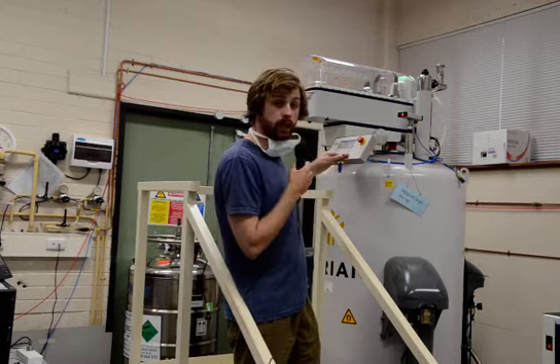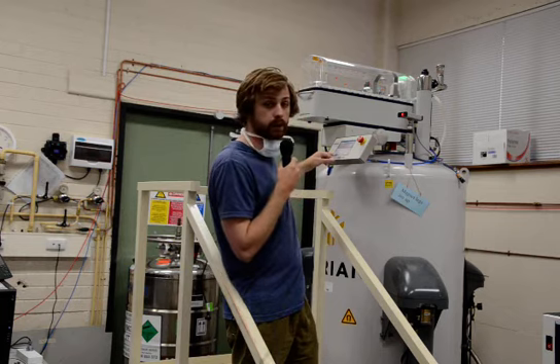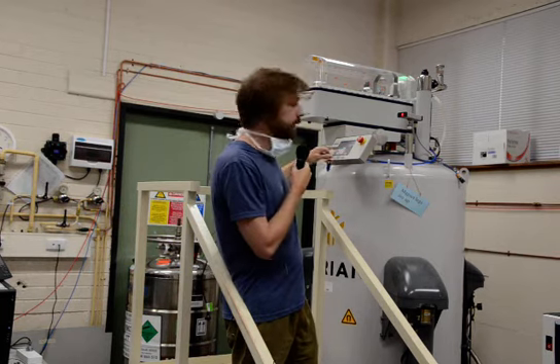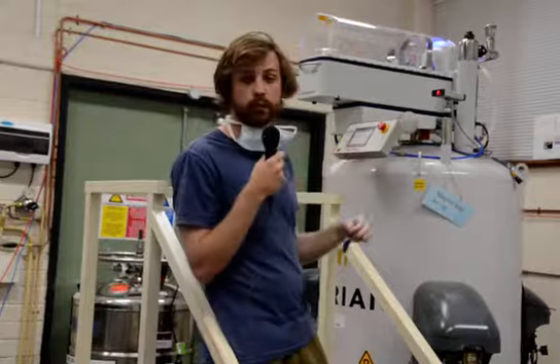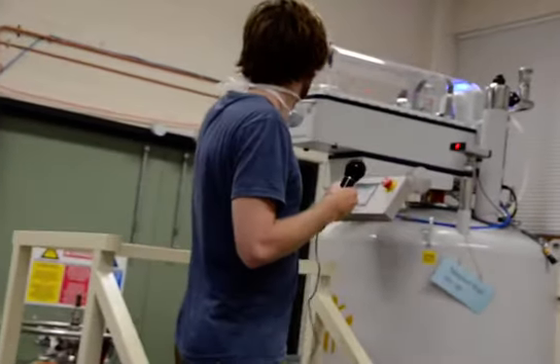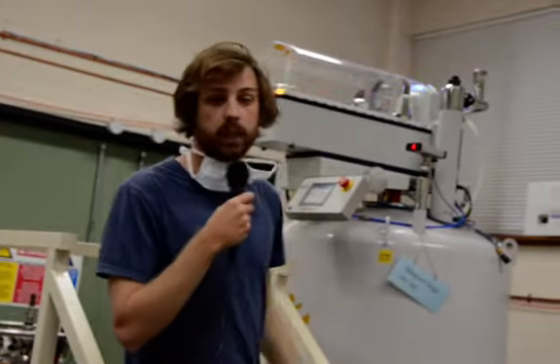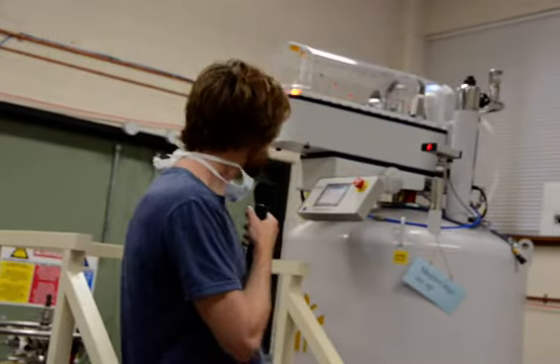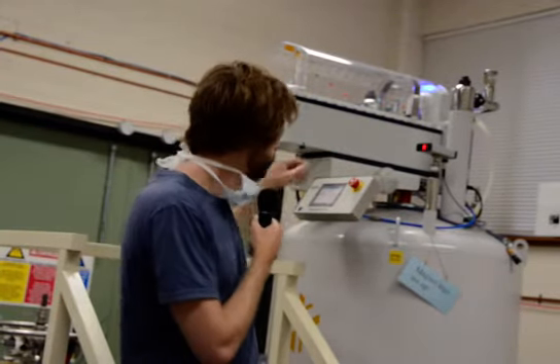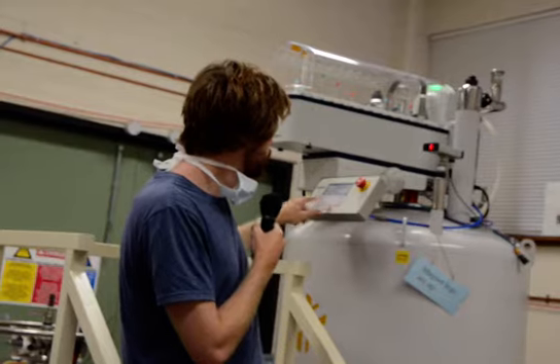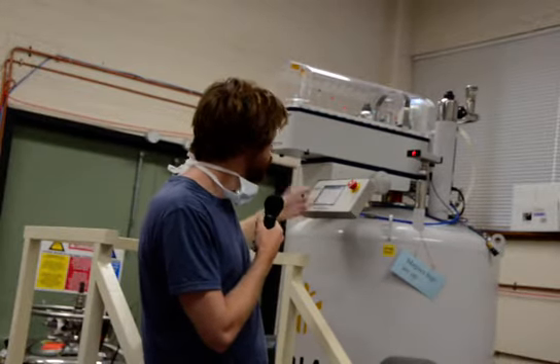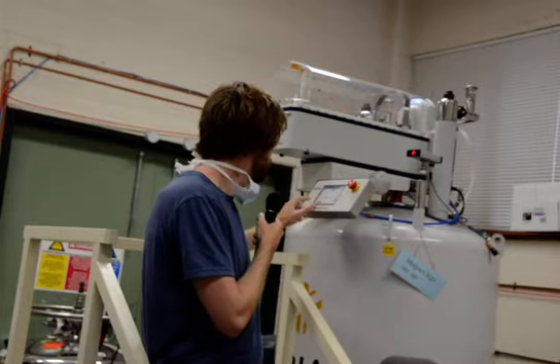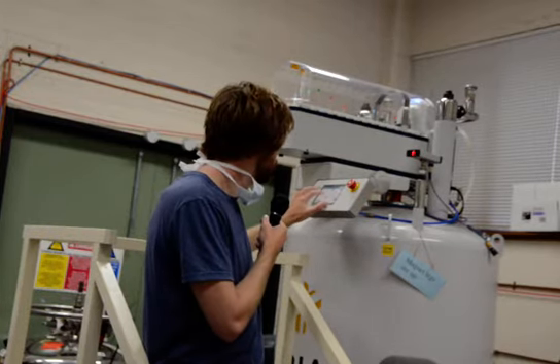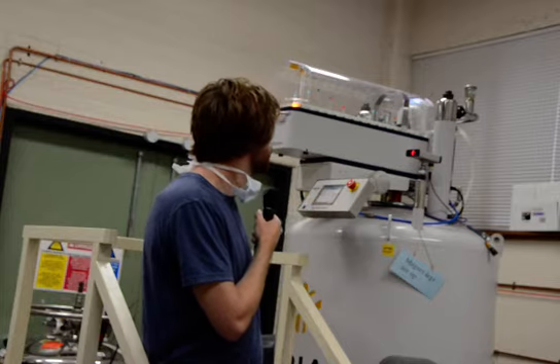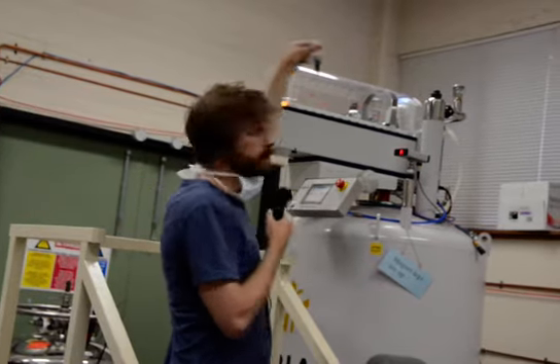So what we're going to do is hit add on the little panel here, which is a little touch screen. We click go to free, so that'll set it up to go to a free sample holder, which it's already at. Place the sample in the spectrometer carefully, and then it's going to go to the next free sample holder. What we can then do is remove the sample too, just by hitting the remove button and then remembering the position of the particular sample. So in this case here, it was 34. And then we can remove the sample when it comes to the front.